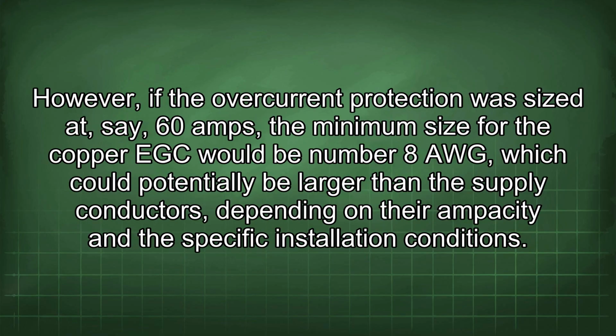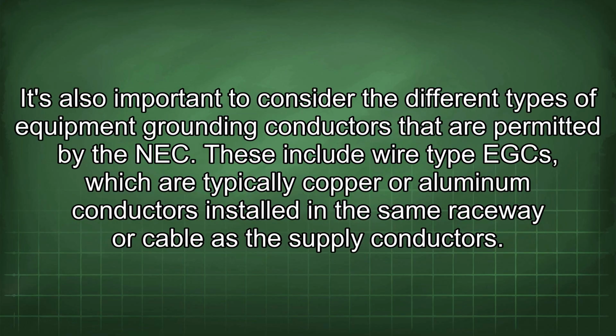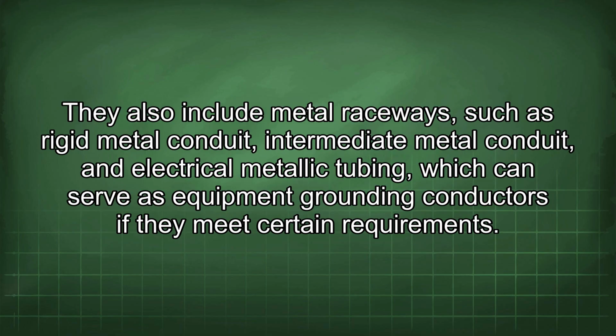However, if the overcurrent protection was sized at, say, 60 amps, the minimum size for the copper EGC would be number 8 AWG, which could potentially be larger than the supply conductors depending on their ampacity and the specific installation conditions. It's also important to consider the different types of equipment grounding conductors that are permitted by the NEC. These include wire-type EGCs, which are typically copper or aluminum conductors installed in the same raceway or cable as the supply conductors. They also include metal raceways such as rigid metal conduit, intermediate metal conduit, and electrical metallic tubing, which can serve as equipment grounding conductors if they meet certain requirements.